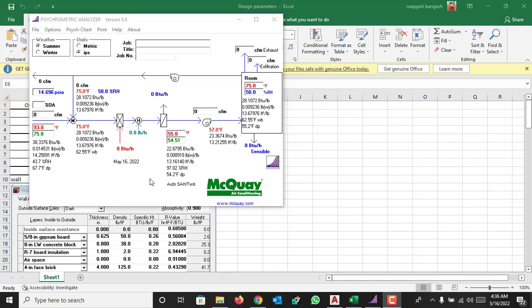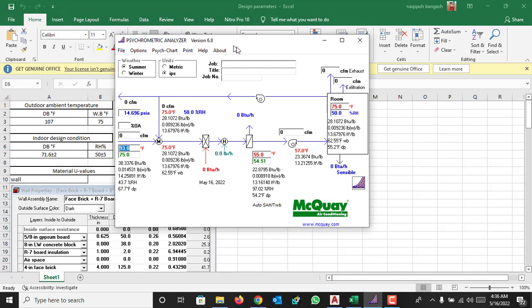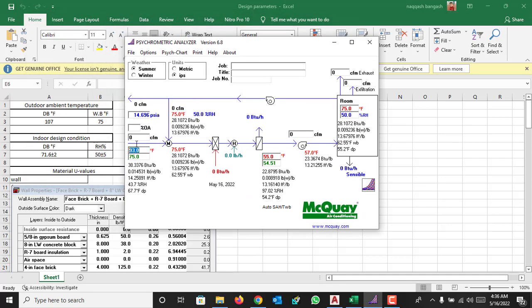How to calculate the cooling coil load if you know the outdoor air temperature, supply temperature, supply CFM or flow rate, so you can easily calculate the cooling coil load. So let's start from an example.